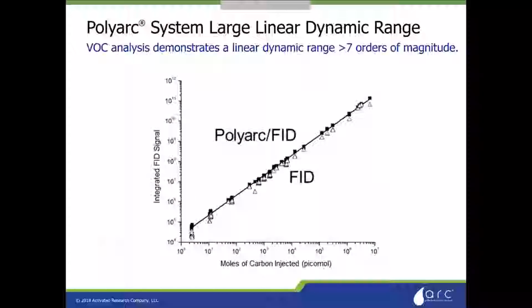Here we have a linearity plot for a variety of VOCs. And this just shows the linear dynamic range of the detector. So we're not sacrificing any of the capabilities of the FID. You're still getting your 7 orders of magnitude range, your low 100 ppb lower limits, and your high 100% injection of solvents. You can still see all of those and run those through the polyarc without an issue.